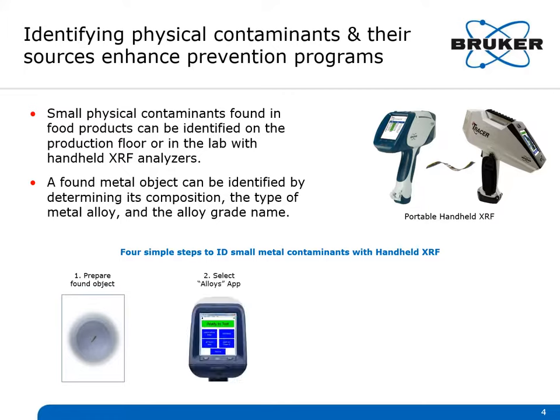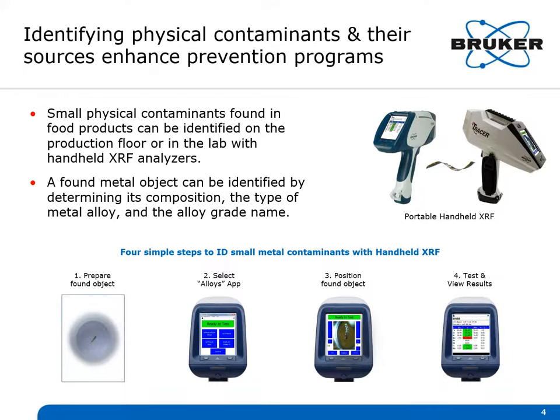There are four simple steps to ID metal contaminants with handheld XRF. First, you prepare the piece of metal in a way that XRF can see it. Then you select the alloys application on the ready-to-test screen. You position the found object to the XRF's window view, start the test, and view the results on the screen — in this case, it's 316 stainless.